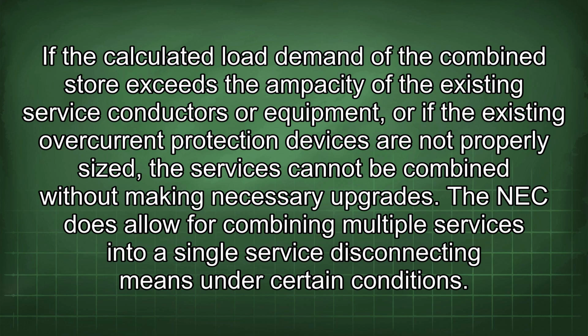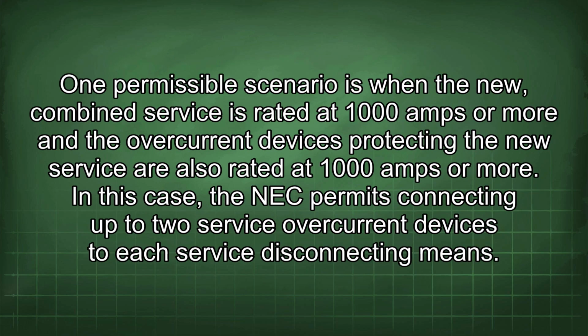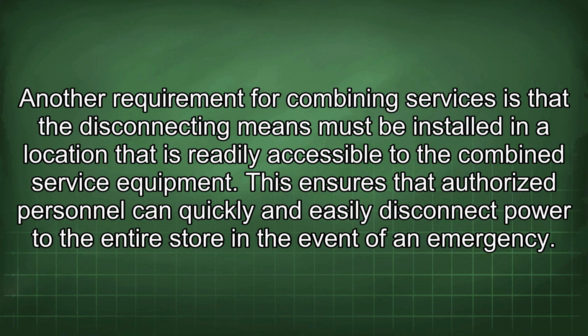The NEC does allow for combining multiple services into a single service disconnecting means under certain conditions. One permissible scenario is when the new combined service is rated at 1000 amps or more and the overcurrent devices protecting the new service are also rated at 1000 amps or more. In this case, the NEC permits connecting up to 2 service overcurrent devices to each service disconnecting means. Another requirement for combining services is that the disconnecting means must be installed in a location that is readily accessible to the combined service equipment.